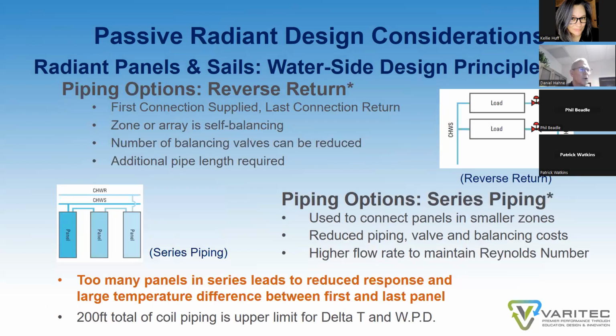There's reverse return, which is the recommended solution. A reverse return piping configuration is first connection supplied, last connection returned. The zone or array is self-balancing. The number of valves in a space can be reduced. However, it does require more piping. So it's sort of a rob Peter to pay Paul with regard to added or decreased cost, depending on the valving and the copper piping, etc.